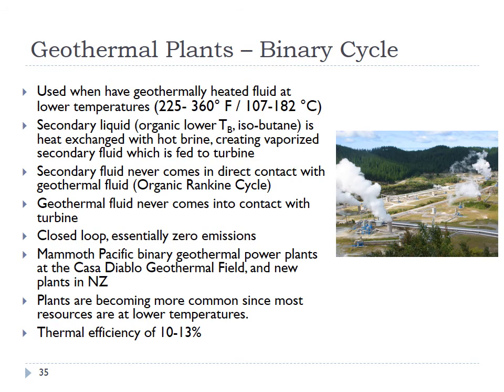Okay, and then finally we have the binary ones. This is typically when you're at 182 degrees C or less. There are a lot of different solvents used out there - one example would be isobutane. It has a lower boiling temperature, which is why it's quite useful. So in this case, our working fluid is isobutane, not water vapor.